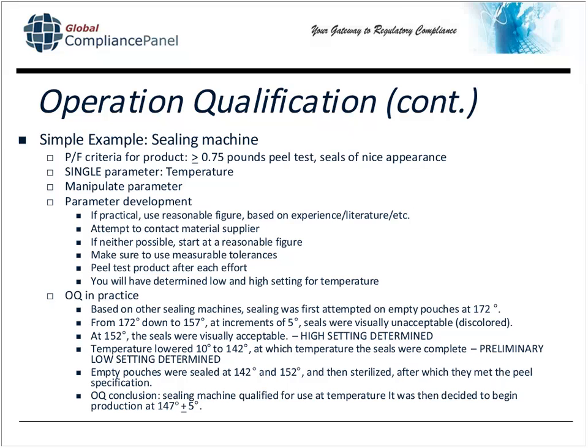So I go from 172 down to 157 at 5-degree increments, and the seals were visually unacceptable. They were discolored, they were blackened. But going down to 152, the seals look good. Voila, I have my high setting at that point. Now I'm going to continue to lower the temperature. So I go down 10, and at 142, the preliminary low setting is determined because the seals were complete.